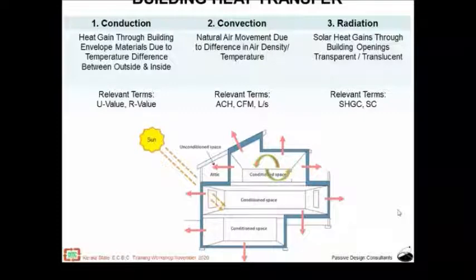The measure or the term used for expressing this heat gain from walls and roof is U value or R value. The U value should be as low as possible in walls and roof, and the reciprocal of U value is R value, which means R value is resistance value, thermal resistance value. The higher the thermal resistance value, the lesser will be the heat gain within the building. So the roof and wall should be designed with a lower U value or a higher R value, by adding insulation materials and insulating construction surfaces to the walls and roof.